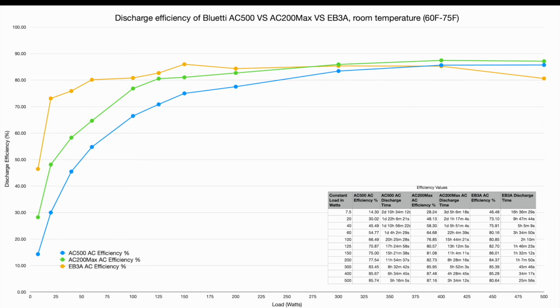So if you're running little loads, recharging your cell phone or a laptop off of AC, getting an EB3A to complement an AC500, having a small solar generator in addition to a large one, will improve your overall efficiency dramatically. If we assume it takes 30% of your power to charge one battery from another, and I'm running at 25 watts on my EB3A as my load, I'm at 75% efficiency versus 30%. So there's a 45% power efficiency difference between the EB3A and the AC500. It's actually more power efficient for me to charge the EB3A from the AC500 and then run my load off the EB3A than to run the load directly off the AC500.